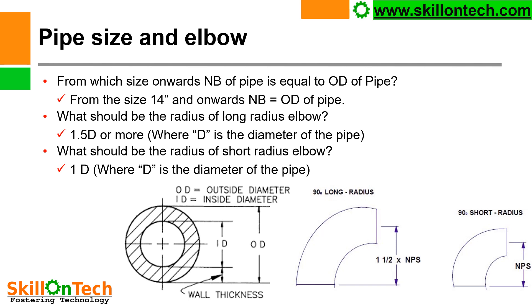Pipe size and elbows — from which size onwards is the nominal bore (NB) of a pipe equal to the OD of the pipe? From 14-inch size and onwards, the OD of the pipe is used as the nominal bore. What should be the radius of a long-radius elbow? Long-radius elbows are 1.5D, where D is the diameter of the pipe. What should be the radius of a short-radius elbow? 1D, where D is the diameter of the pipe. Pictures of long-radius and short-radius elbows, and the ID/OD of pipe with wall thickness, are shown for reference.